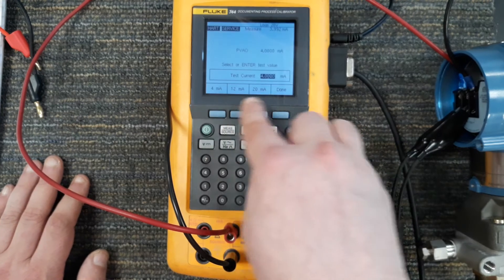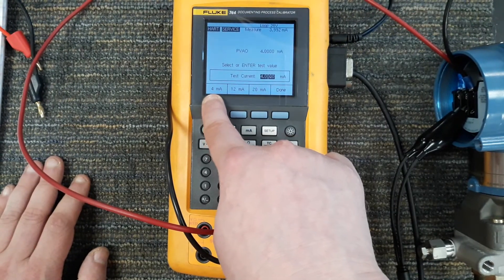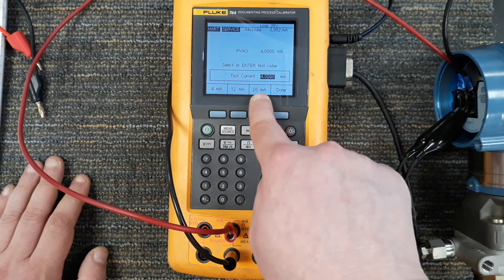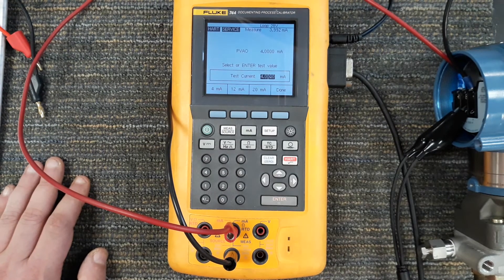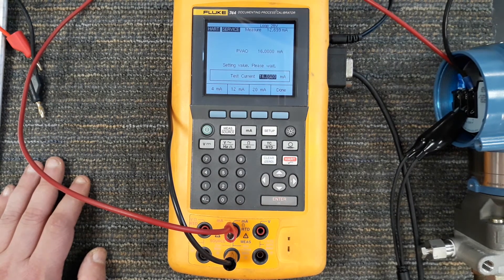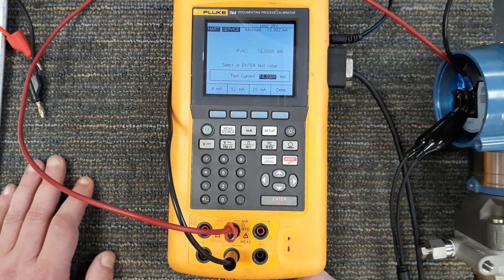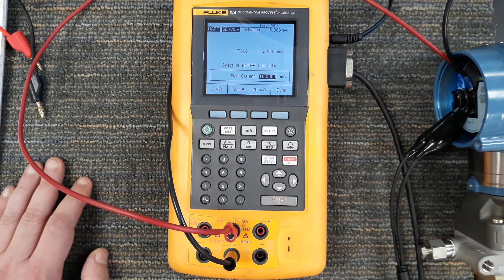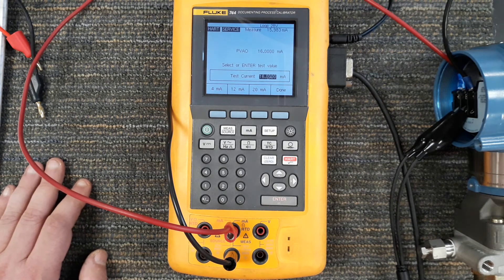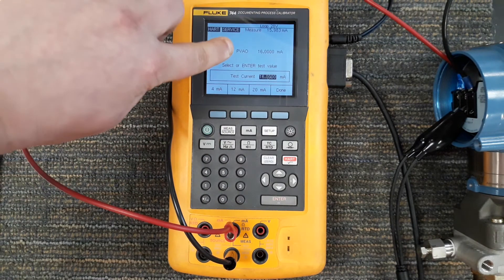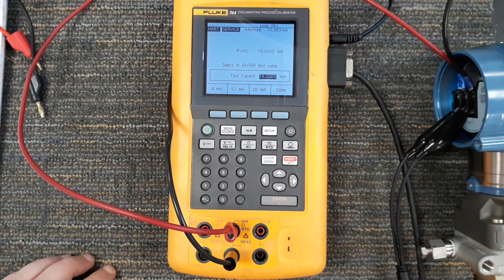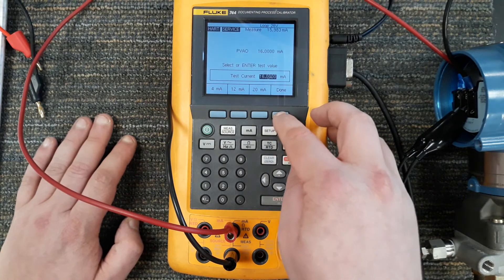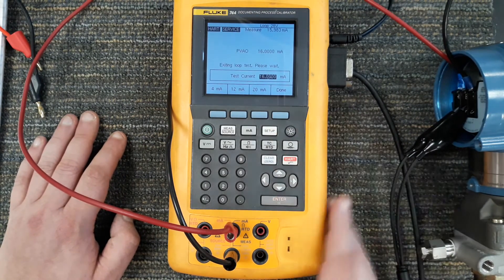You see the standard: we got zero which is actually four milliamps, 50% is 12 milliamps, 100% is 20 milliamps, or I can type in the exact value if I want, 16 milliamps which is 75%. This thing would try to manipulate the current on the loop to be 16 milliamps and it's saying the process analog output is 16. I'm going to hit done.